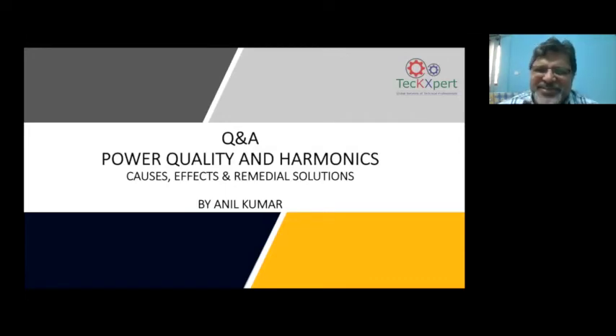Now coming back to your grounding: grounding is the way to protect the equipment as well as protect the people. Many times you have harmonics produced by harmonic producing loads like AC drives and LEDs. AC drives can be kept away for the time being. The LEDs and other single phase electronic loads produce a lot of third harmonic current. The third harmonic current naturally flows through the neutral, and it can go into the ground also, depending on the capacitance between the neutral and the ground. We call those noises.